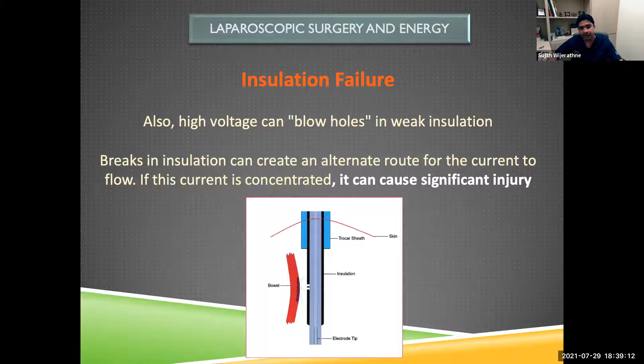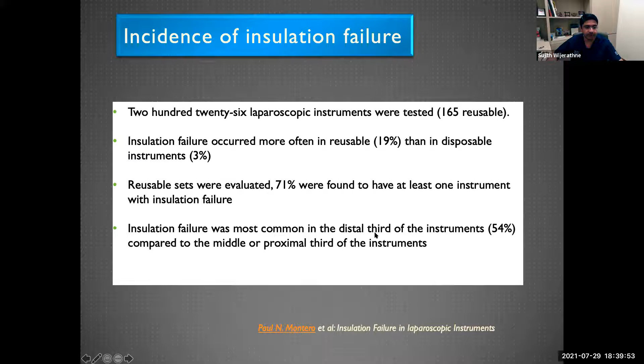The incidence: about 226 laparoscopic instruments were tested in one of the studies, and insulation failure occurred more often in reusable instruments. We all use reusable instruments, and most of our endolaparoscopic equipment is actually reusable. In the reusable sets, when they evaluated them, 71% were found to have at least one instrument with insulation failure. And this insulation failure was more common in the distal third of the instruments compared to the middle or the proximal third.